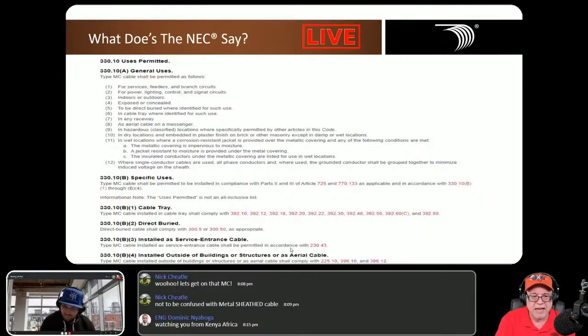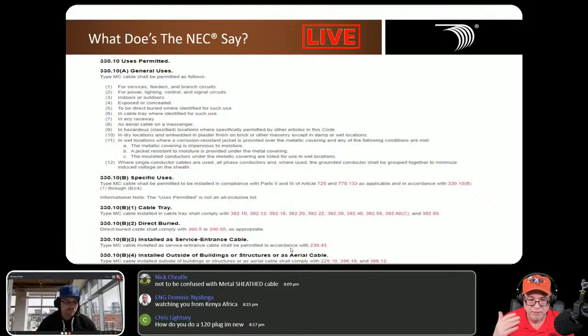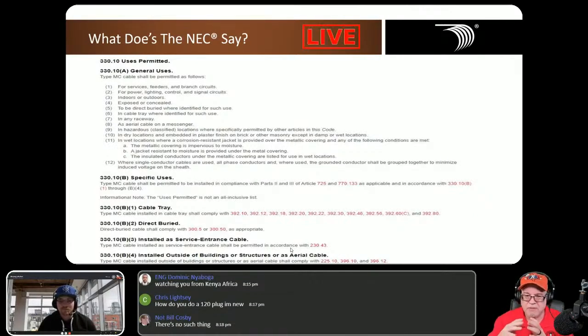And incidentally, a lot of people ask about flame ratings. So MC cable that goes into a cable tray is going to have a flame rating of UL 1685 method 1, which is a 70,000 BTU test. That's all that's required. Now, some engineers will want it to be something like an IEEE 1202 or FT4, and that is not the same as a UL 1685 method 1. That's equivalent to a UL 1685 method 2. And it just happens to do with how much charring you can have and the angle of the burner, and all of that changes a little bit. But you're not required to have it be more enhanced like an FT4 or anything like that. You know what I'm saying? It's only required to meet the minimum requirement, and that would be 1685 method 1.